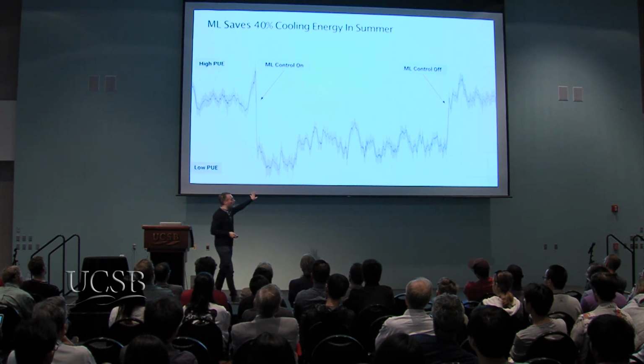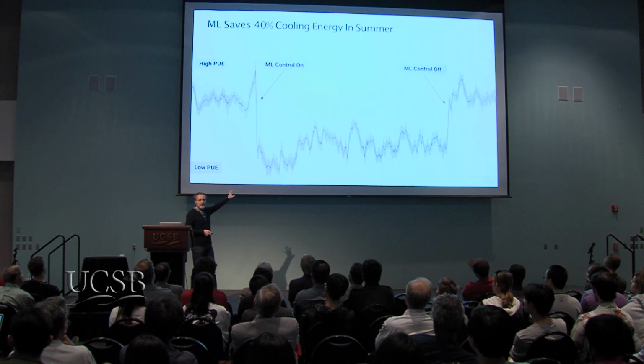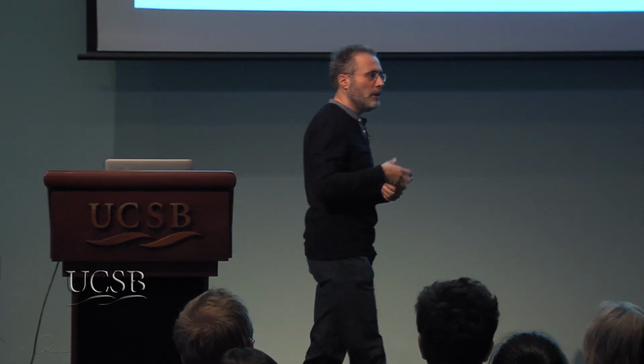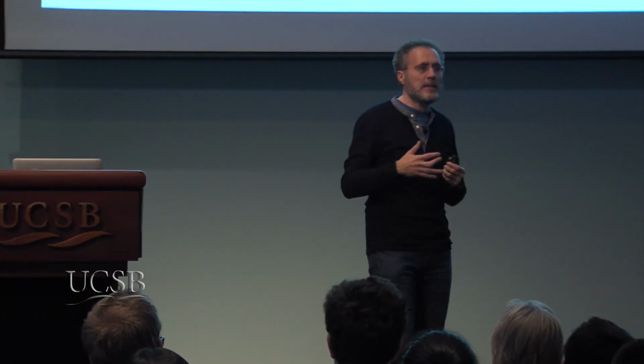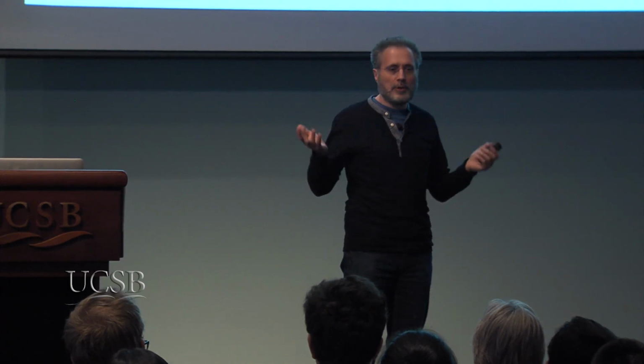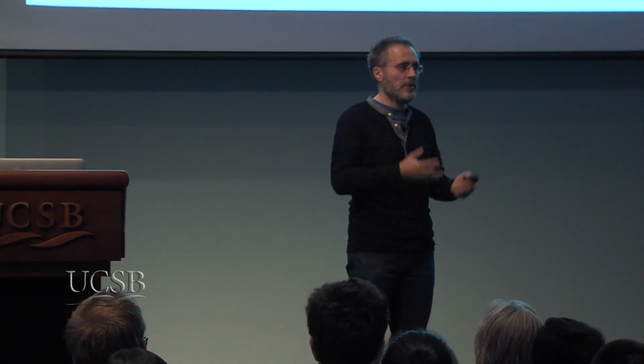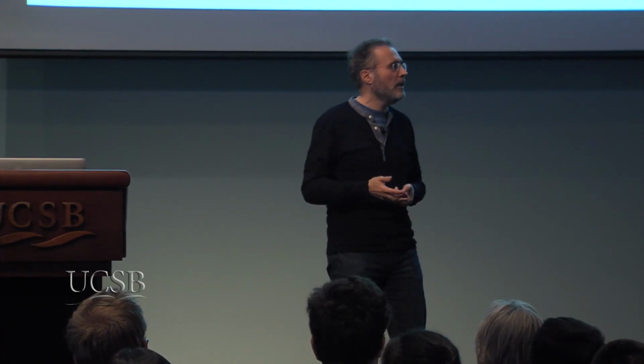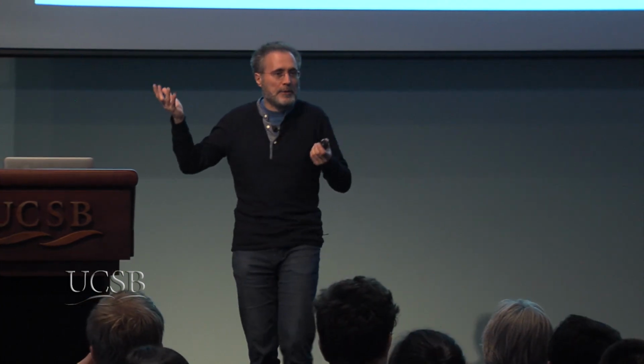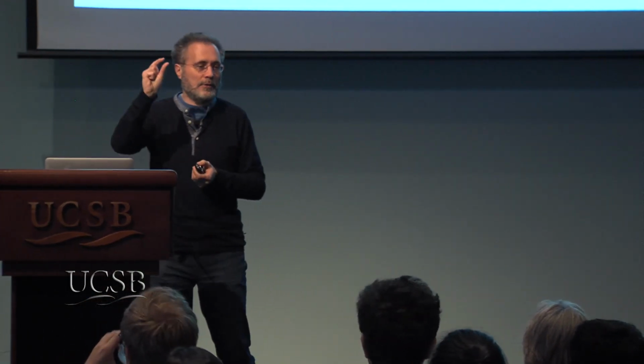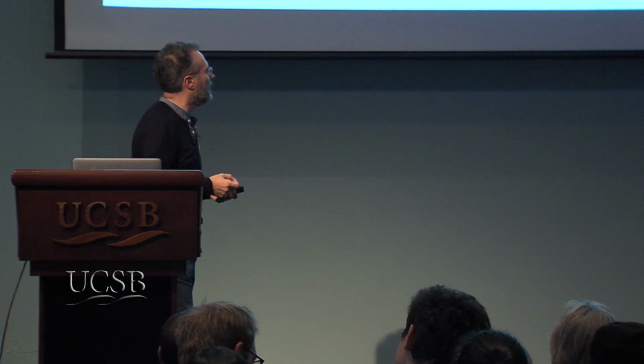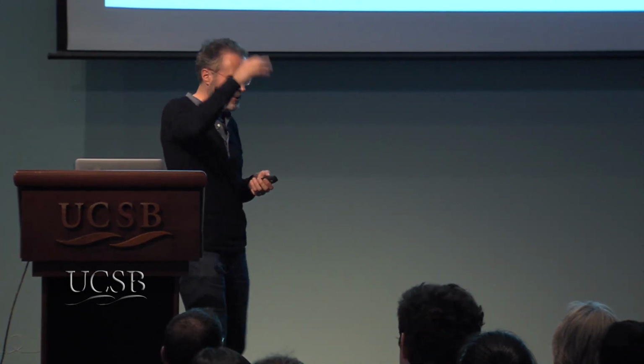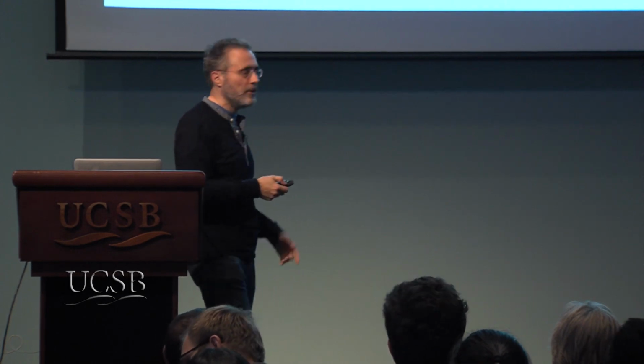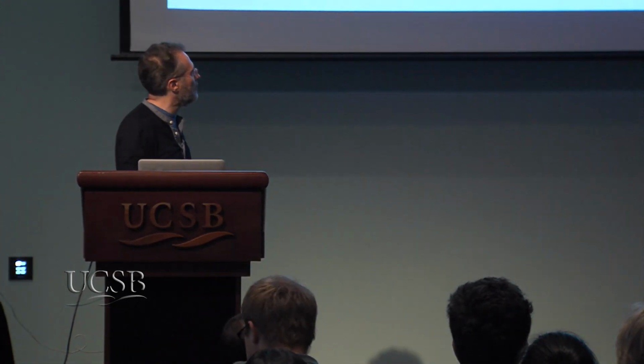Last caveat: this is only in the summer. In the winter you don't see that, because in a cold location you spend so little on cooling - it just works, one cooling tower is on, the pumps are at lowest speed, it's cold outside, so everything just works and you can't really save much there. But we're very excited about this, and you see our worldwide average curve. We're now introducing this in all the buildings, and we're going to see that drop by another 10% or so.